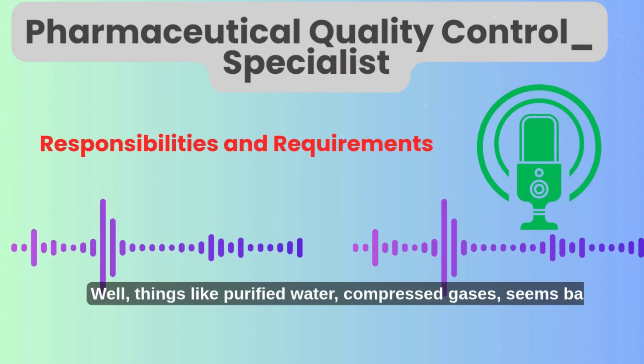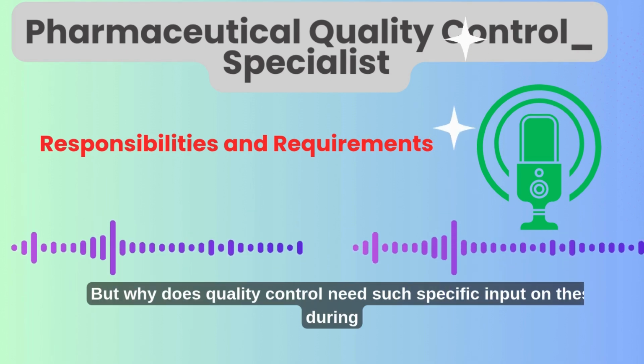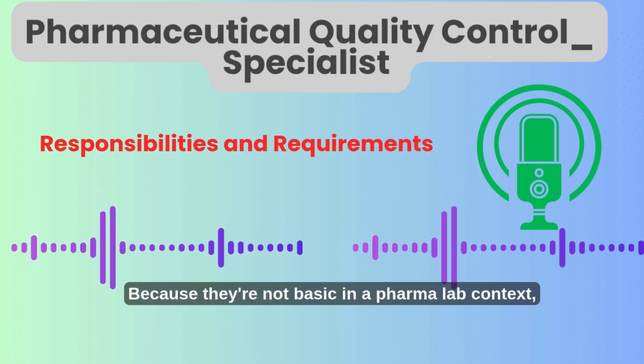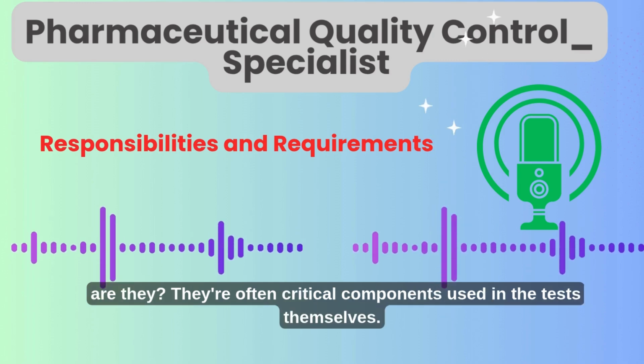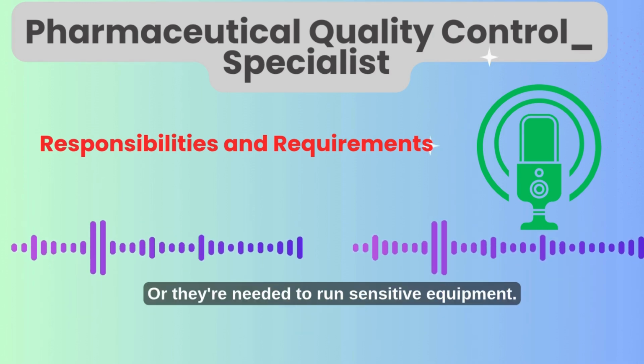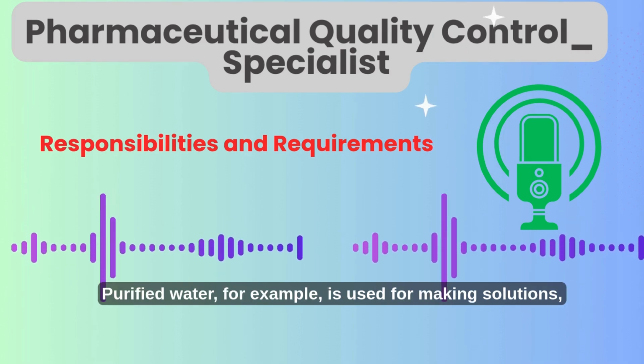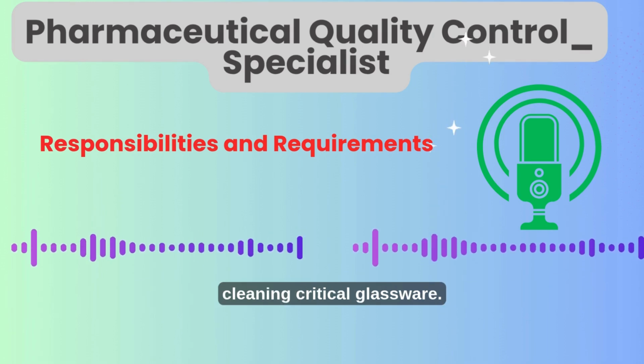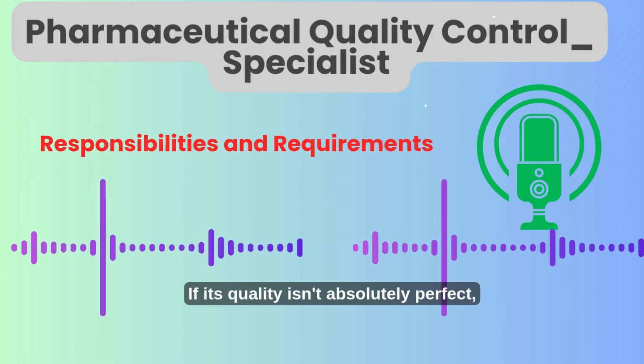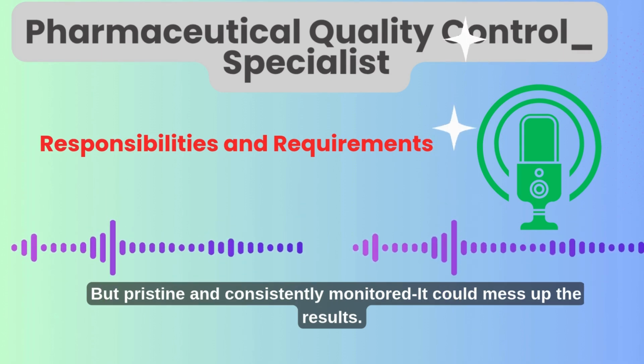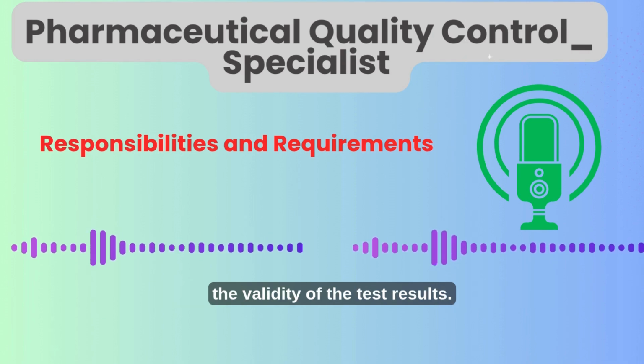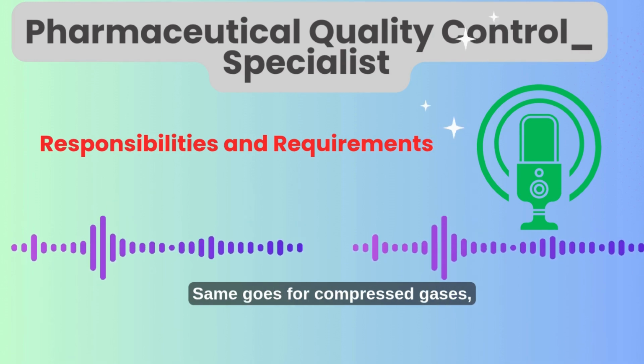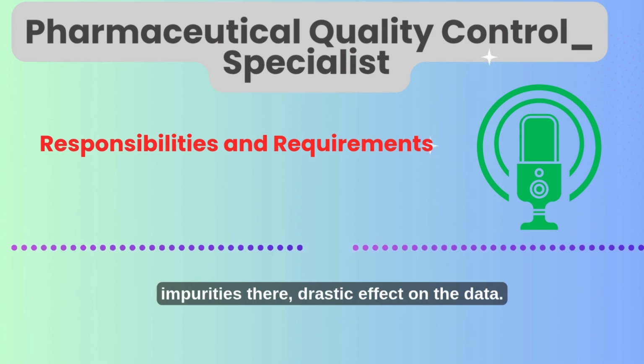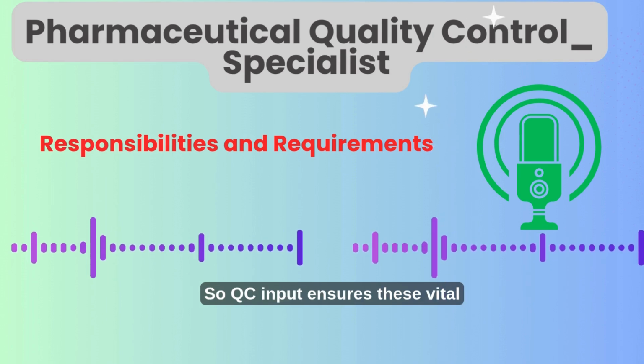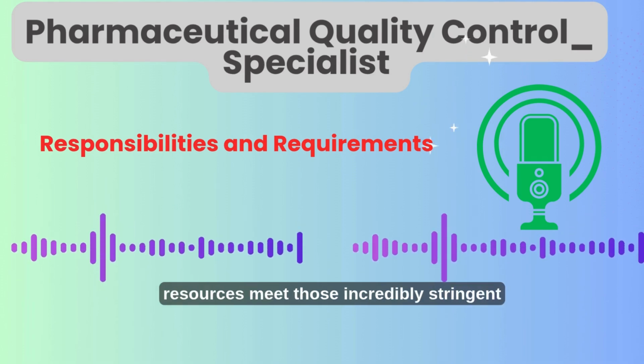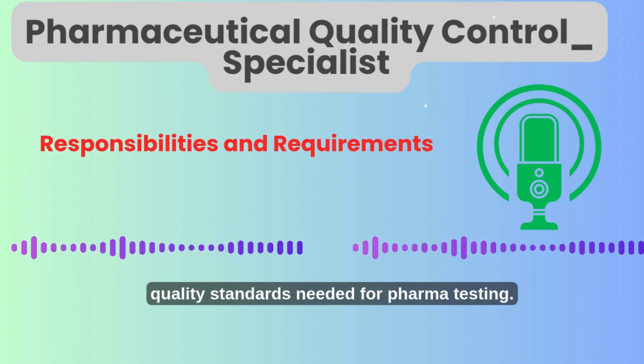Things like purified water and compressed gases seem basic, but why does quality control need such specific input on these during design? Because they're not basic in a pharma lab context, are they? They're often critical components used in the tests themselves. Precisely. Or they're needed to run sensitive equipment. Purified water, for example, is used for making solutions, cleaning critical glassware. If its quality isn't absolutely pristine and consistently monitored, it could mess up the results. It can compromise the accuracy and the validity of the test results. Same goes for compressed gases, often used in things like gas chromatographs. Impurities there have a drastic effect on the data. So QC input ensures these vital resources meet those incredibly stringent quality standards needed for pharma testing.